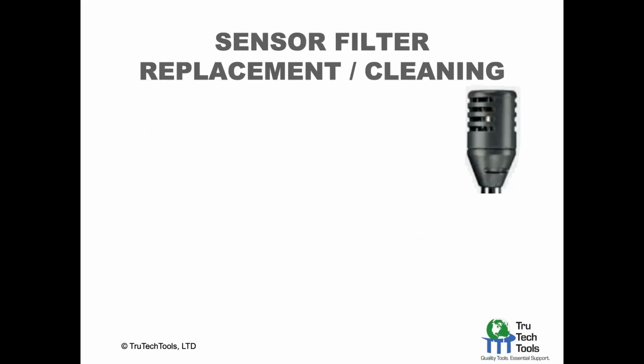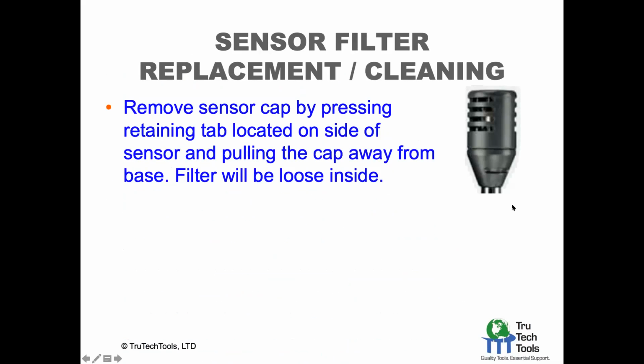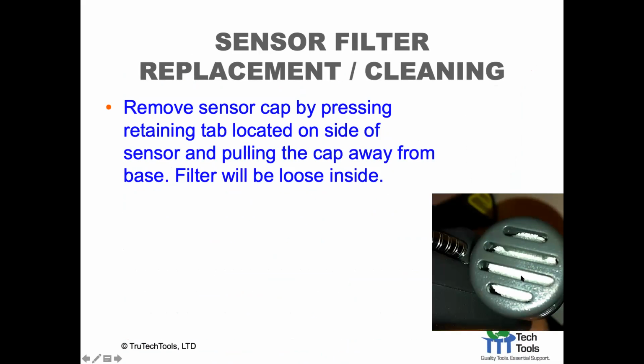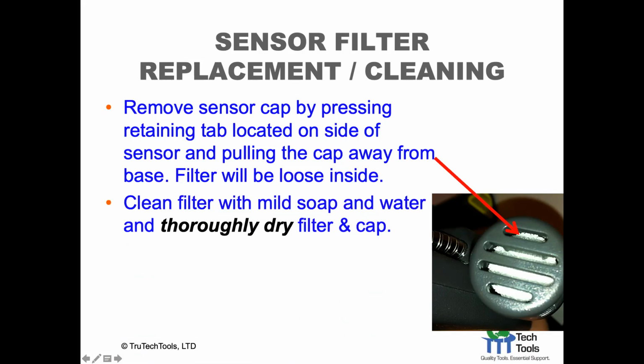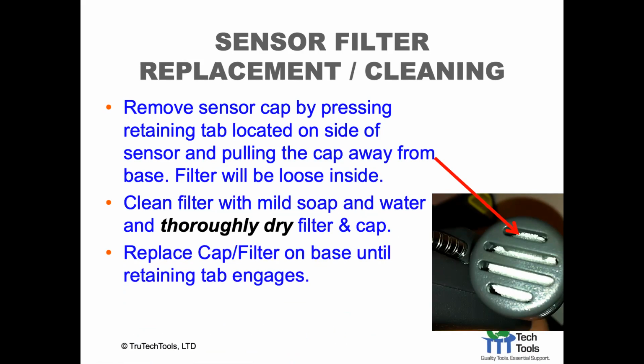So you can change the sensor filter or change the sensor itself. You remove the sensor cap by pressing the retaining tab, which is located on the side of the sensor, inside this cap area, and pull it up and away. There's a disc filter, which will be loose inside. That's the filter, a little pre-cut material. So you want to clean that area. If it looks contaminated or dirty, clean the filter and the cap with mild soap and water, and make sure it's thoroughly dry before you reinstall it. Then put the cap on inside the base, and slip it over the top of the base until the tab clicks back in place.